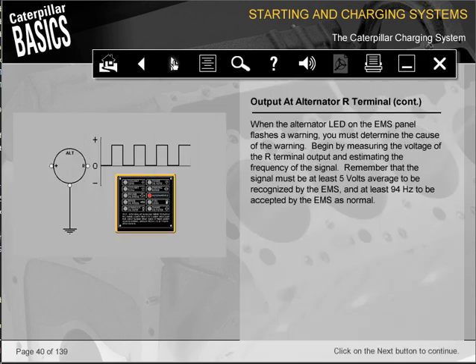When the alternator LED on the EMS panel flashes a warning, you must determine the cause of the warning. Begin by measuring the voltage of the R terminal output and estimating the frequency of the signal. Remember that the signal must be at least 5 volts average to be recognized by the EMS, and at least 94 Hertz to be accepted by the EMS as normal.